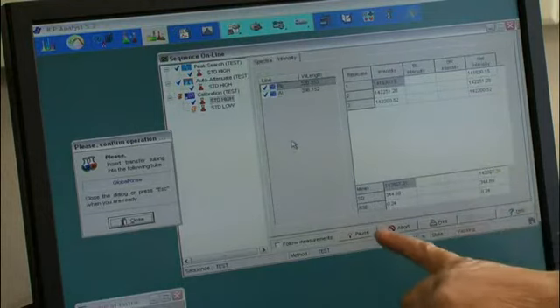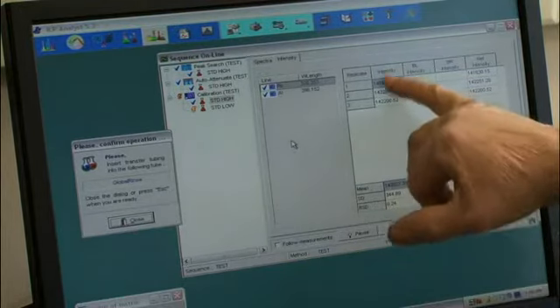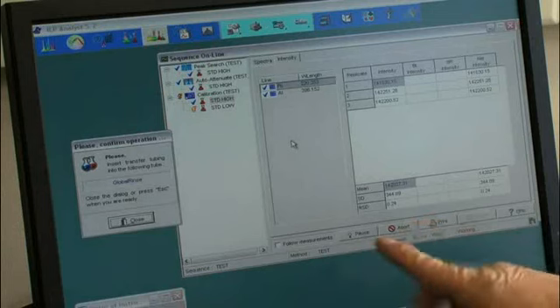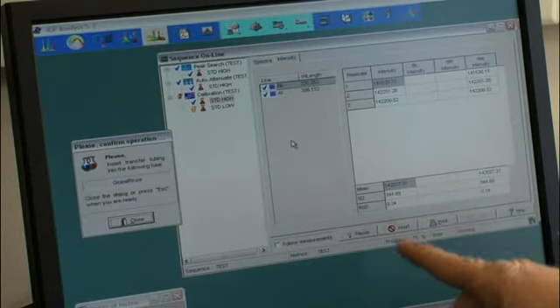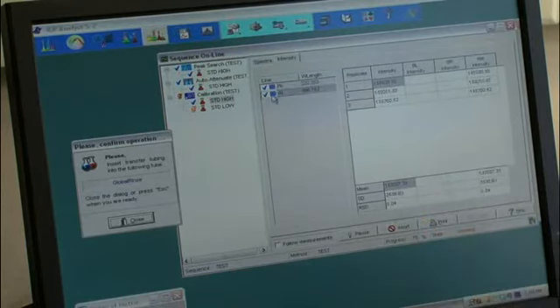So here you can see what your RSD come out to be according to the 3 measurements. So anything below 1.5 is good, so that's pretty good. That's a little high. So let me put in the blank, do that.